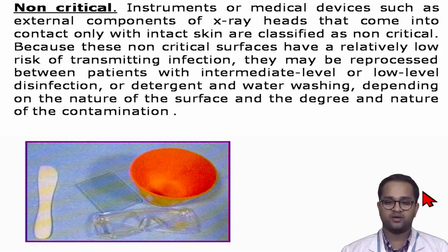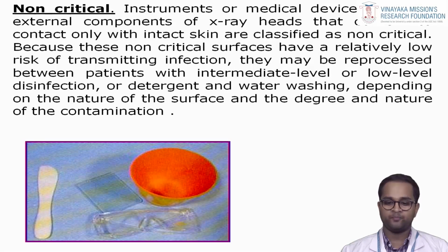Coming to non-critical, instruments or medical devices such as external components of X-ray heads that come into contact only with the intact external skin are classified as non-critical. Because these non-critical surfaces have a relatively low risk of transmitting infection, they may be reprocessed between patients with intermediate level or low level disinfection or even a detergent or water splashing or washing, depending on the nature of the surface and the degree and nature of the contaminant.